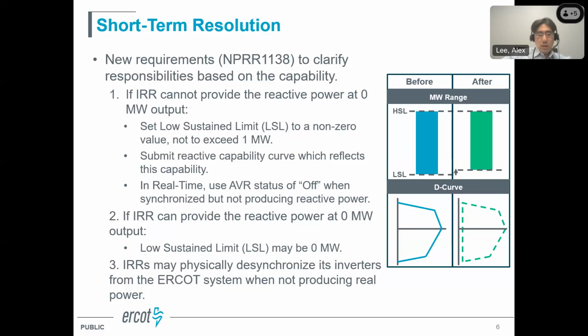Furthermore, once they make those changes and correctly reflect their capability, they should submit or update their reactive capability curve, the D curve, correctly to ERCOT. Lastly, in real time, when they're having 0 megawatt output, they can just simply turn off the AVR and they can desynchronize the inverters if they want to.